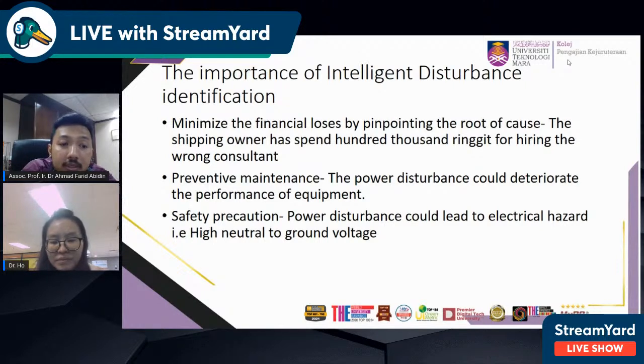And the last one is safety precaution, where power disturbance could lead to electrical hazard, such as high neutral to ground voltage. High neutral to ground voltage means there is a voltage that appears between the metal enclosure and the ground. So when you touch that metal enclosure, it can trigger current, and the current could flow through your body because there is voltage over there. The voltage could come from the high neutral to ground voltage. So the safety precaution can also be related to power quality issues.